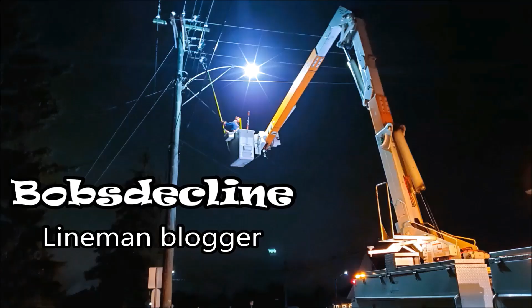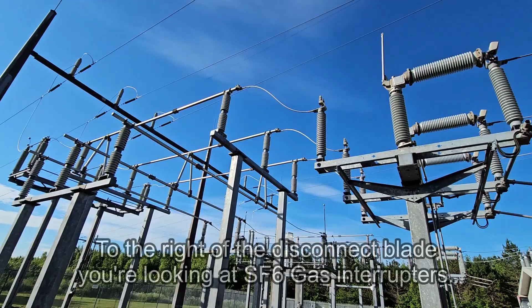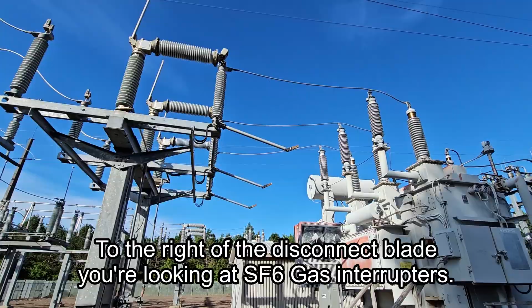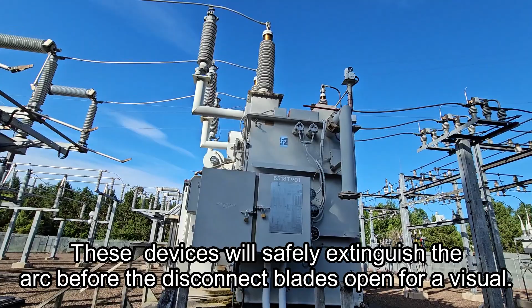But let's check out a few clips that I did manage to capture. Alright guys, so this is going to be a super quick video because I'm waiting for a call from my dispatcher. But we had our high side circuit breaker open. It's 138,000 volts. That switch opened under fault. The call actually came in that the substation was on fire, so you can imagine what was going through my head as I was driving here, but it ended up being not a huge deal. That switcher is protection for the transformer itself. If there's a failure, that guy pops automatically. It's all electronic. And then it feeds 3 feeders going into our town here, about 2,600 customers.